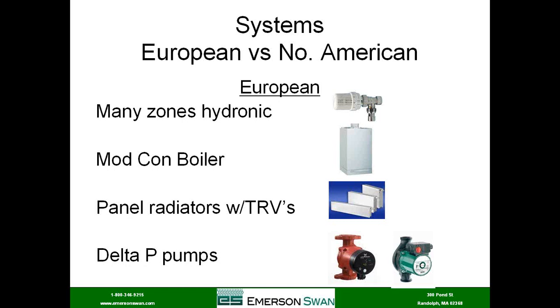So the pump is set for worst case scenario, which is all of these open, and as these valves close down, which they do, again, if the temperature in that area of the radiator increases, the valve closes, the pump senses a drop in pressure, the pressure changes, and it slows down to accommodate that. And the valve opens up, it speeds up. So basically, it's speeding up to fill a pipe with holes, fill a hole with water. You've got a pipe with lots of holes in it, and a hole opens up, and it speeds up to fill that hole with water, and it works perfectly. It's an absolute perfect application pump for that application. Perfect. And if that's what you have, that's the pump that you should use because it's the right component for that system.